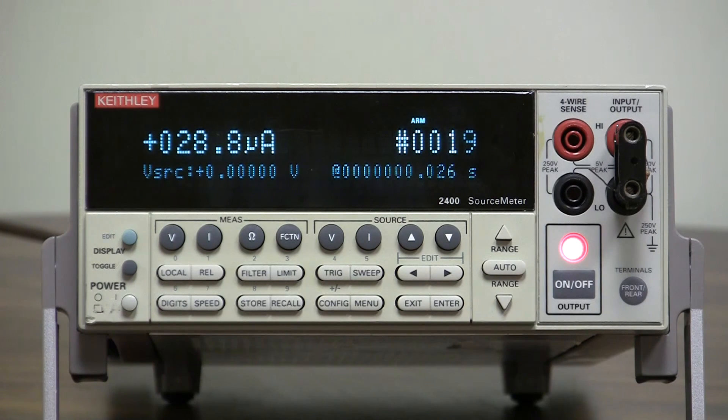So your voltage pulse is about one point something milliseconds. That's the fastest you can get from the front panel controls on a model 2400.